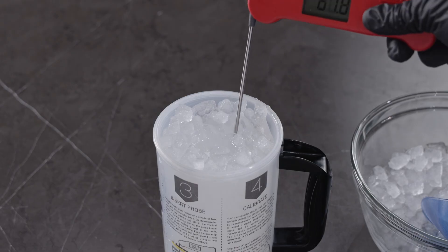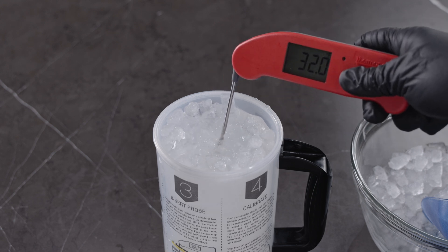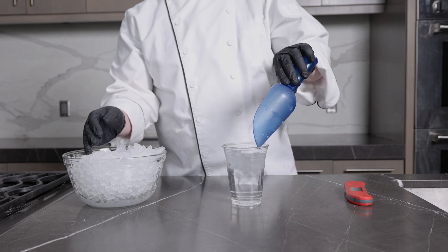That said, if you want to test any thermometer, an ice bath is a reliable test as long as it is prepared properly. Most ice baths are created improperly and give inaccurate readings.